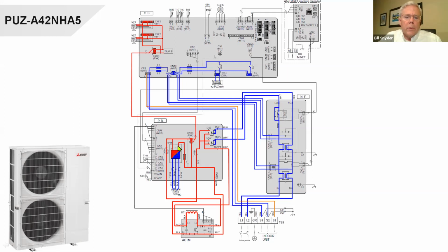Okay, now we come in here with DC. We come out with 3 AC power lines that would connect to U, V, and W on the MC, which stands for motor compressor. That's the compressor. So we have 3 distinct AC voltages coming out here. The voltage varies and the frequency varies of that.